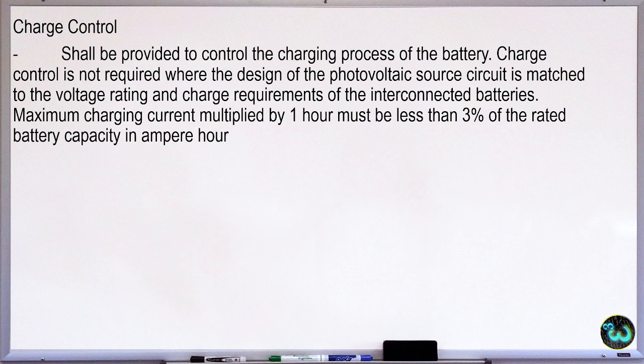The maximum charging current multiplied by 1 hour must be less than 3% of the rated battery capacity in ampere hours. So that is the 1 hour. So the maximum charge current, for example 3 amperes times 1 hour, the answer must be below 3% of the ampere hours of your battery. So that is also to prevent overcharging.